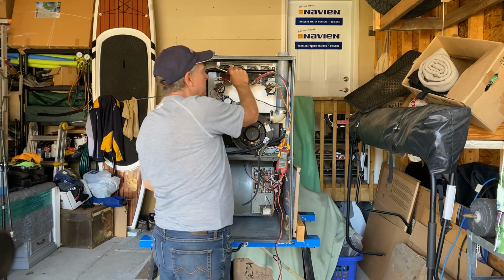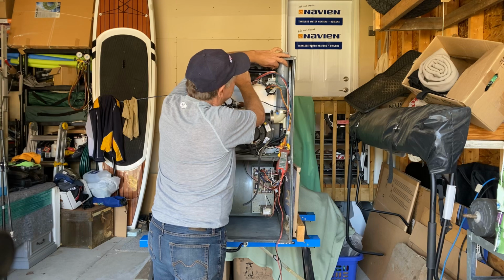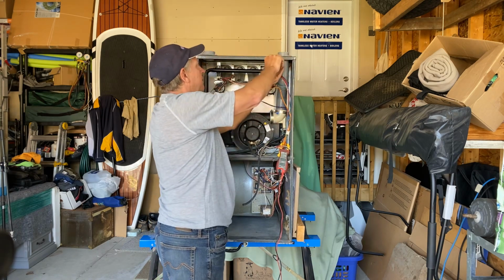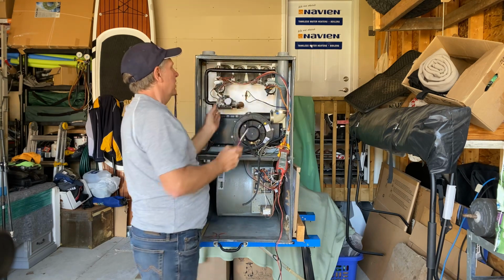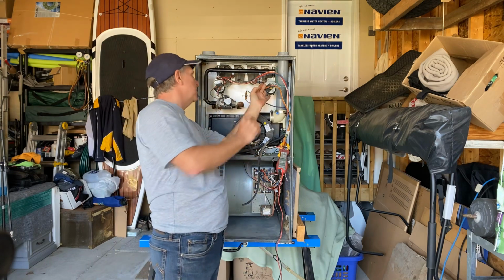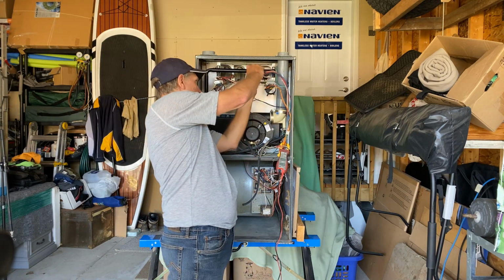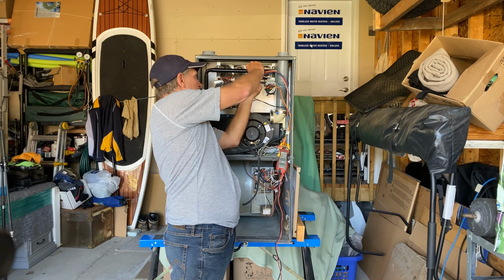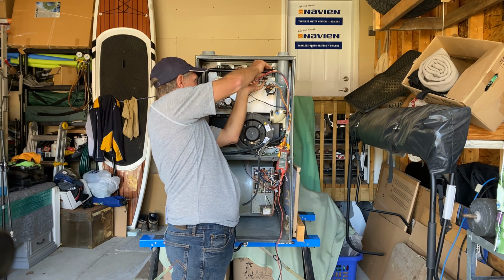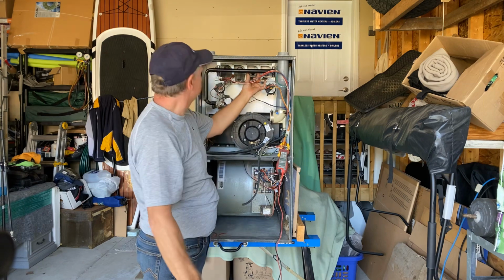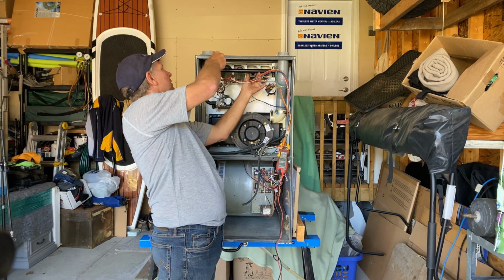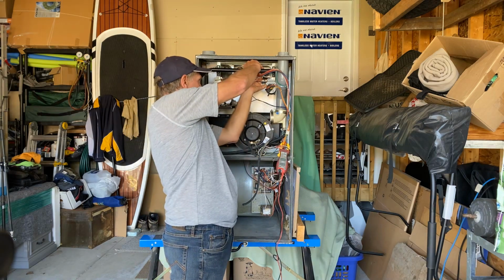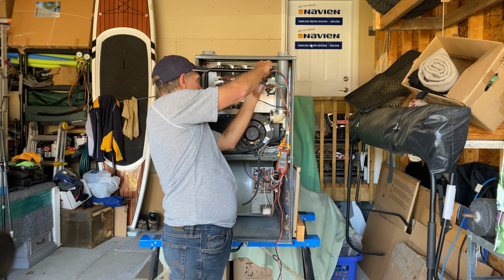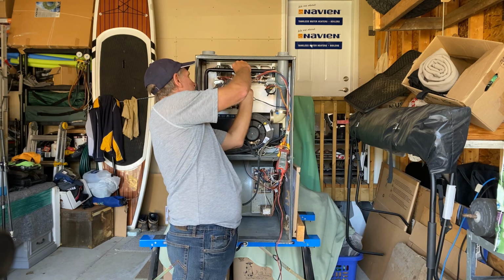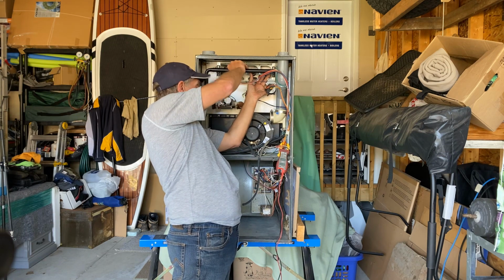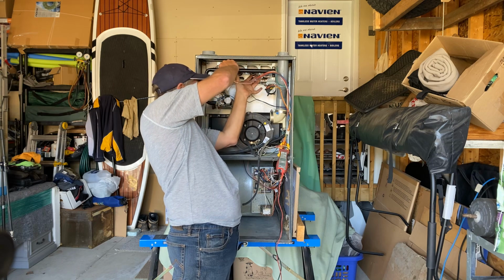So 4 screws basically hold this burner assembly in place. It's a little bit tricky. What I've found is you put the 2 screws in the top first, and you've got a little bit of a lever action there because these burners need to be pushed back up so that the venturi is back onto the orifice. So a little bit of a trick there, getting that sorted out and getting them all in place. Here is getting the 4th one, and then the other 3 don't fall out.